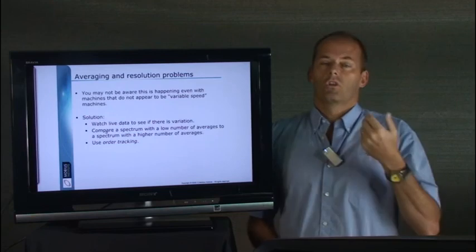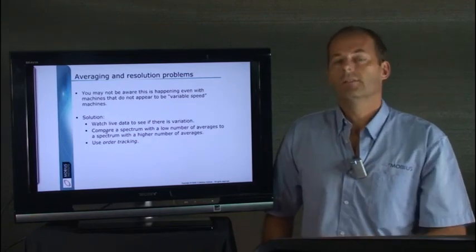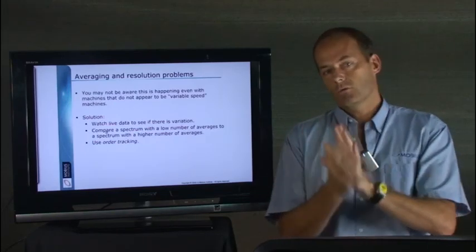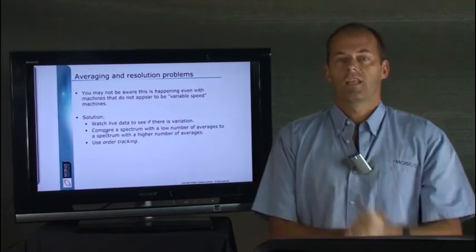But the true solution is to do something called order tracking. You need a tach signal from the machine and the analyzer actually synchronizes its acquisition with the speed of the machine. But that's another topic altogether.